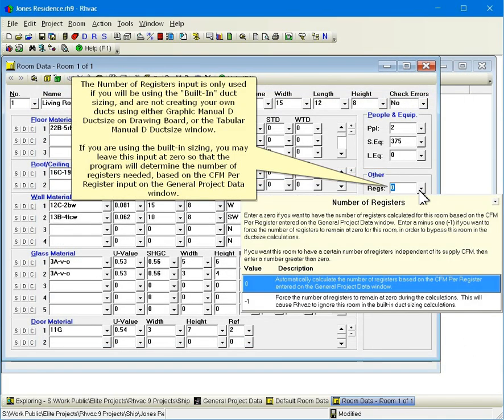The number of registers input is only used if you will be using the built-in duct sizing, and are not creating your own ducts using either Graphic Manual D duct size on drawing board, or the Tabular Manual D duct size window. If you are using the built-in sizing, you may leave this input at zero so that the program will determine the number of registers needed based on the CFM per register input on the general project data window.